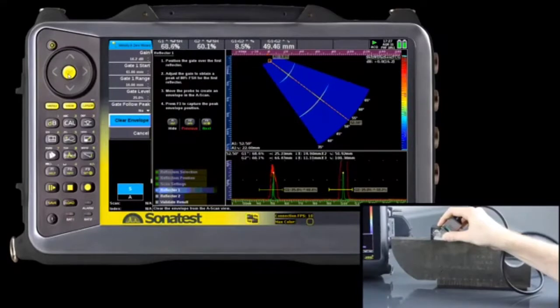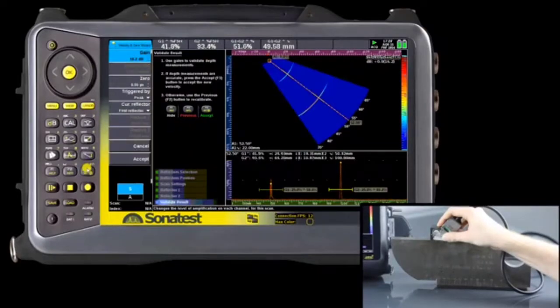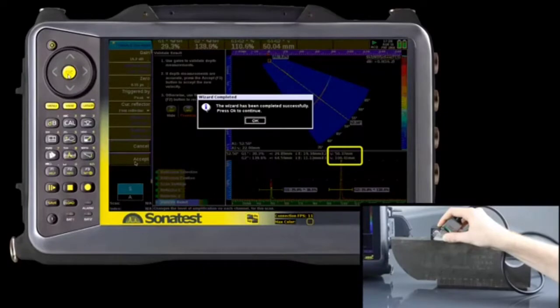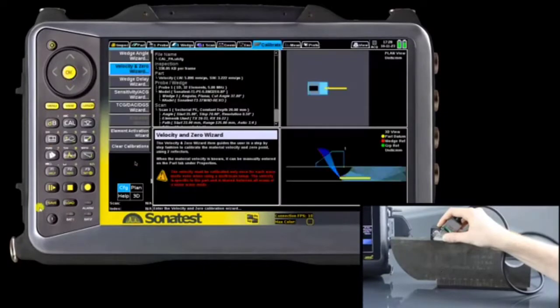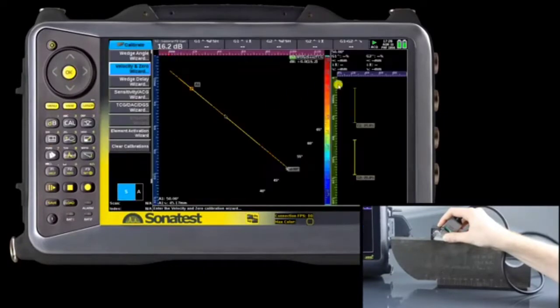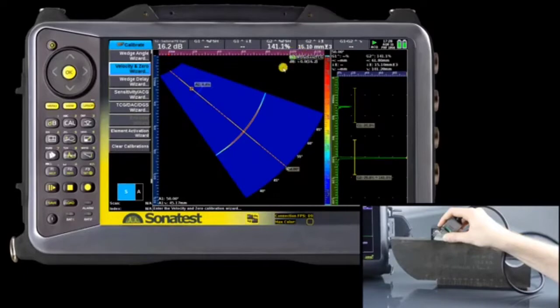Finally, click twice on the F3 button to go to the validation window. To confirm your velocity value, check the path measurement of both your gates in the A-scan. Always make sure that the calibration speed is close to the theoretical value of your material speed. Finally, the velocity calibration sign will turn green.